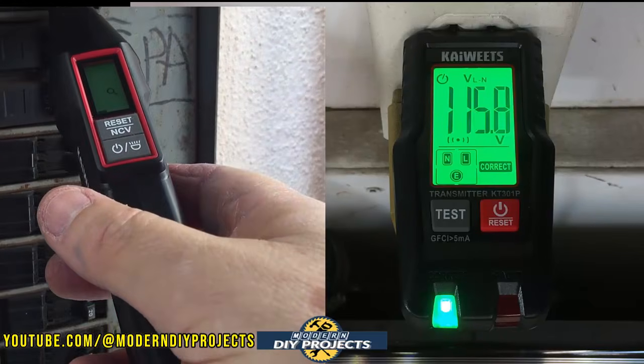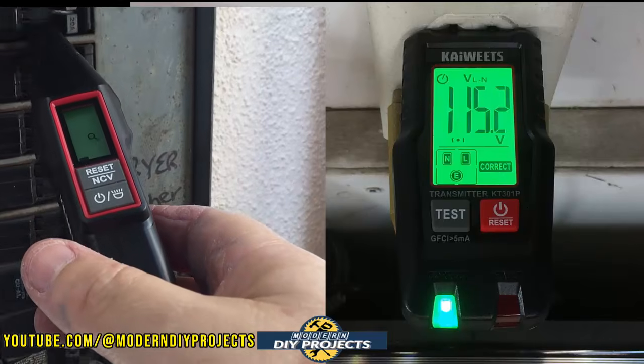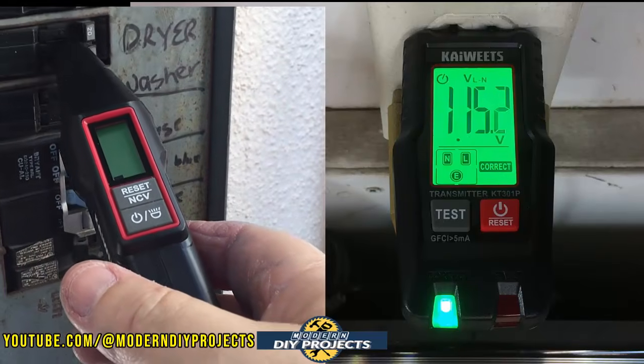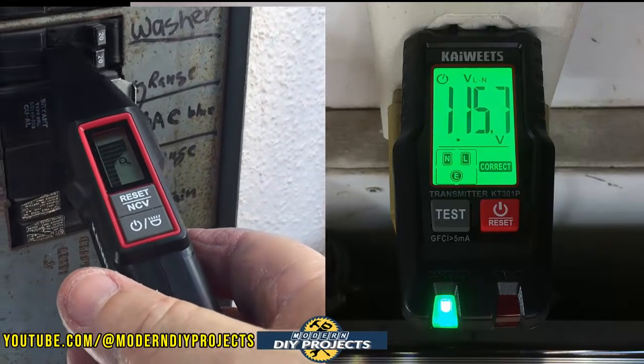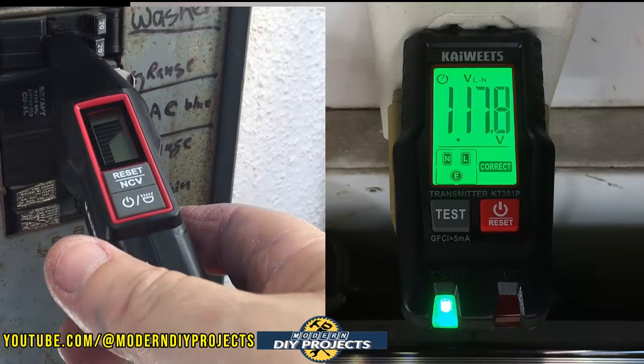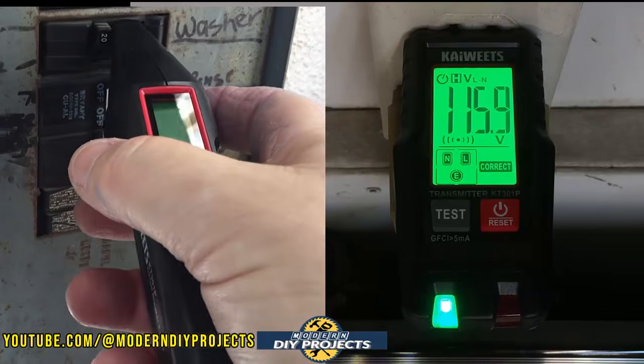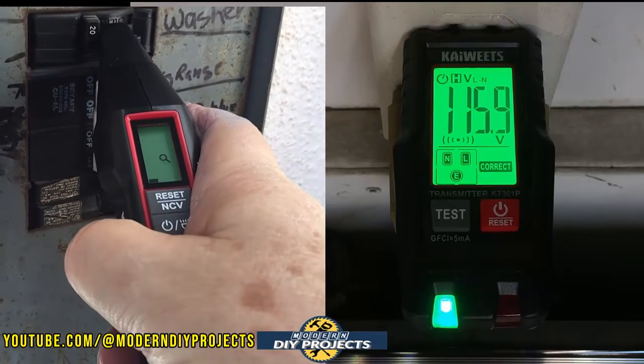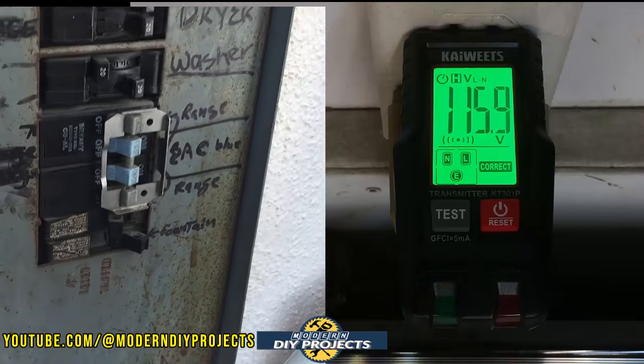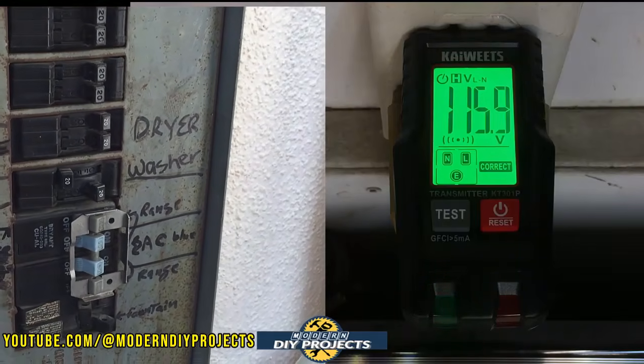The main will always give you a false reading, so ignore that top one. So you scan all the way down, and right there, that's where it tells you we found it. I'm going to turn it off, and you'll see the one on the inside start blinking, telling you that the circuit has been turned off. You see no more power on there, so it means it worked properly. So there you go.